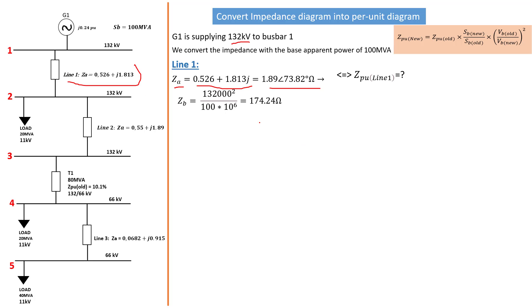Filling up the formula, ZB is equal to 174.24 ohm. Since we already know the value for ZA, we're just going to replace into the Z per unit formula. That gives us 0.011 with an angle of 73.82 degrees per unit. So that is now the Z per unit for line 1.